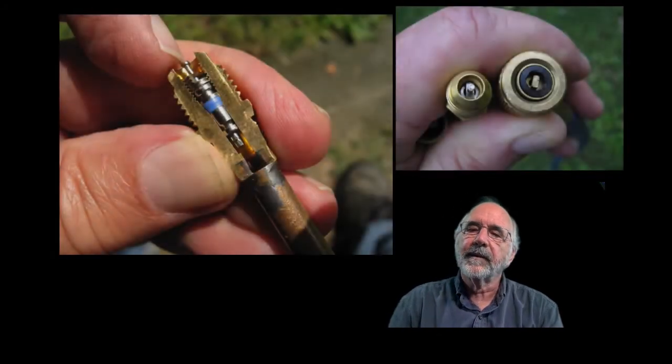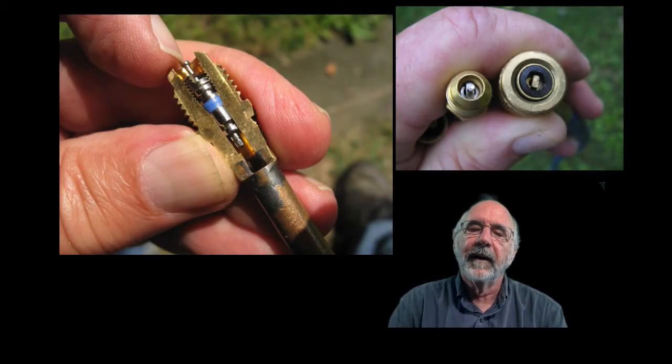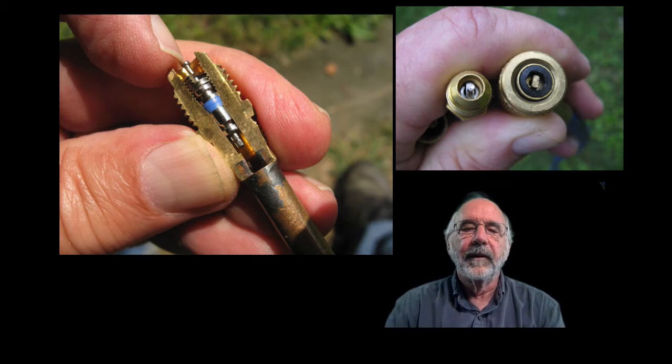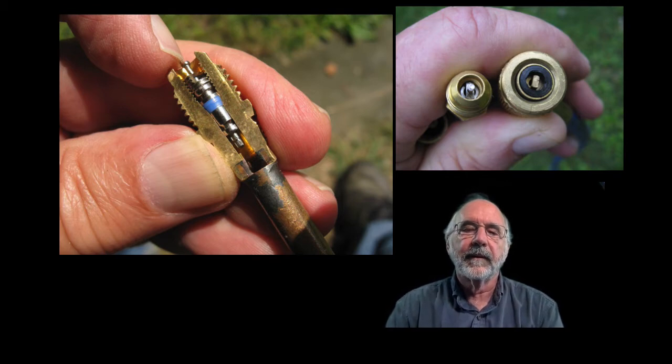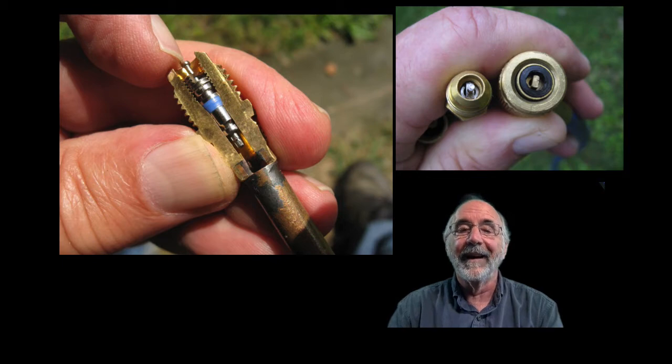Take a look at this cutaway view of a service valve. Leaving the core in and having to use a core depressor in the hose blocks the already small opening off by more than about 90 percent.